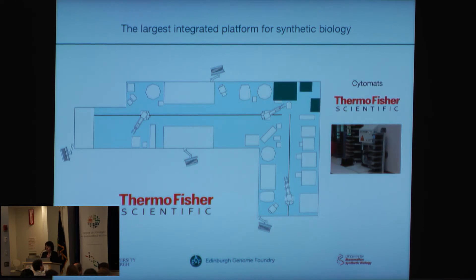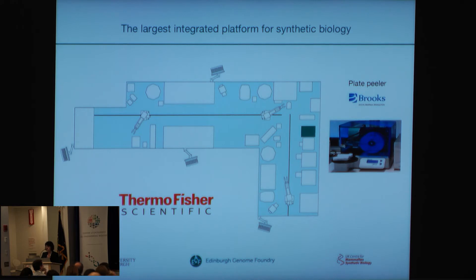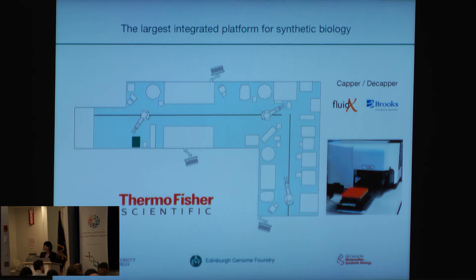Also various incubators at adjustable, changeable temperatures for reagents or cultures — yeast or bacteria. We also have centrifuges on the system, plate sealers to seal the plates. All reactions are performed in SBS plate format that can be handled by them, and the plates need to be sealed. There is also a peeler to peel the seal off for further processing. Then we have various de-lidders on there as some plates don't have seals, for example the agar plates for the colonies. And we have a capper/decapper as we freeze all our parts and assembly constructs in glycerol stocks in FluidX tubes.